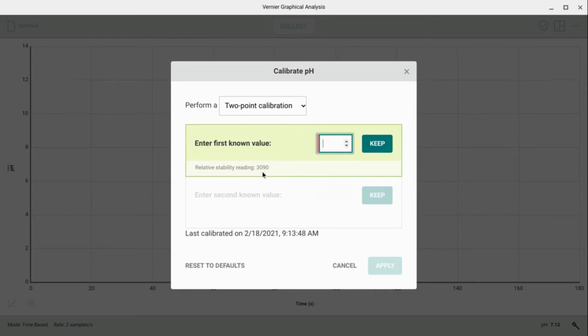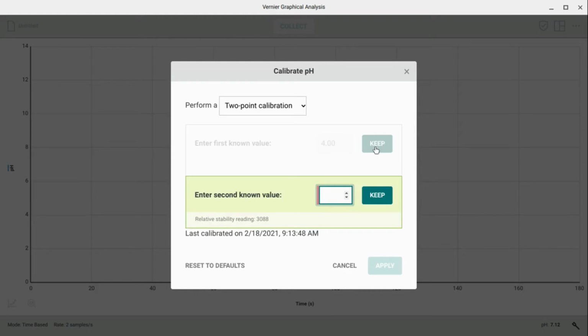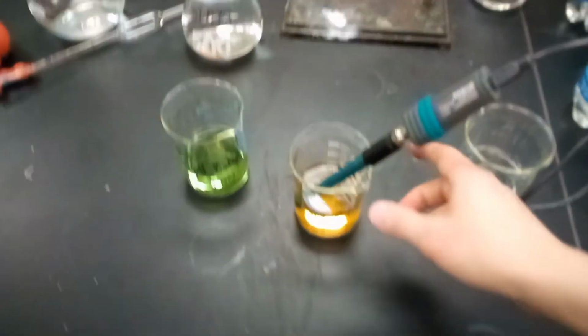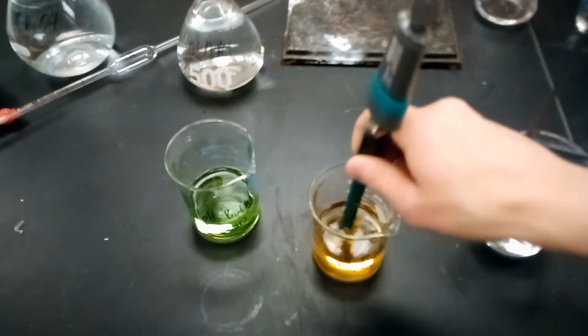So here we are. Hopefully you can see here that the stability reading is alternating between a few numbers, but it means that it's pretty close to being accurate. So we can put in the value that we know this to be, 4.00. We'll press keep, and then we need to go to the second one using the pH buffer of 7.00. So we're good with the 4.00 buffer.